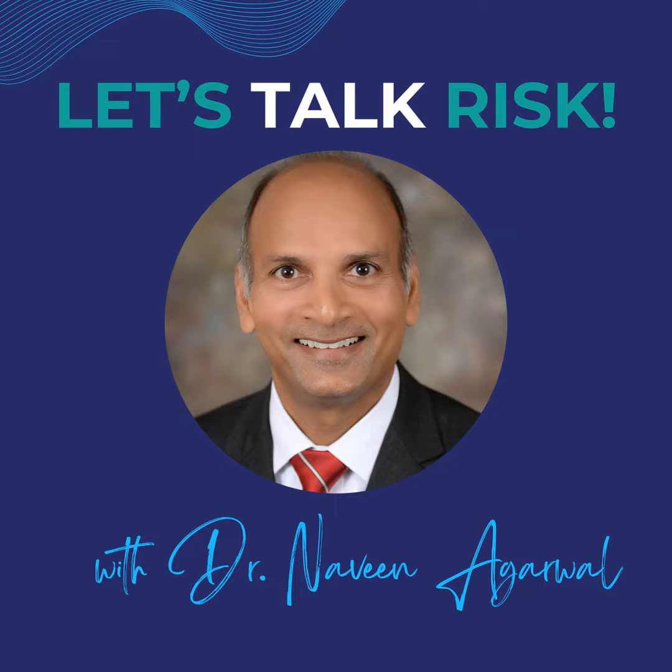So I think in a startup environment, it's challenging to take a step back because everything has to go very quickly because we've got to be in market as soon as possible. But sometimes it might be worth spending a little bit of time upfront and doing that hazard analysis that Ed talks about, starting with the hazards. Can you even not do something in a way that gives you more hazards, right? Just eliminate some of those hazards right up front. So design choices can be made later on appropriately. Does that make sense, guys?